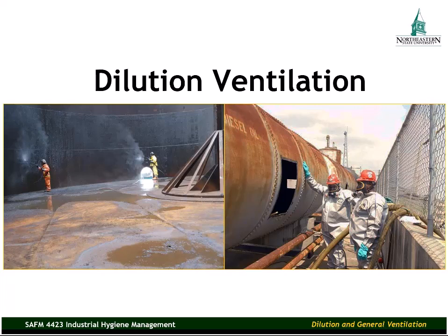Now, dilution ventilation is different. A lot of the same components are used. A lot of the same principles apply to dilution ventilation. But with dilution ventilation, the focus is not on collecting the contaminant at its source. The focus of dilution ventilation is to dilute the contaminants in a work area.